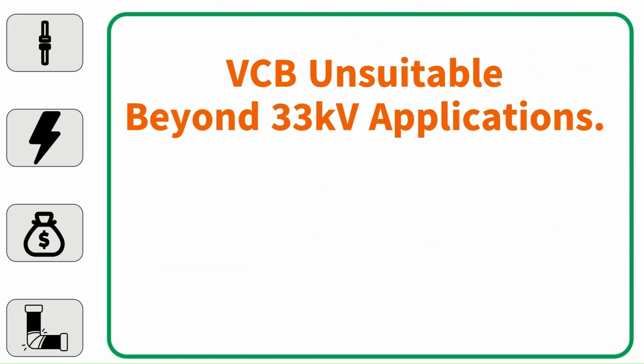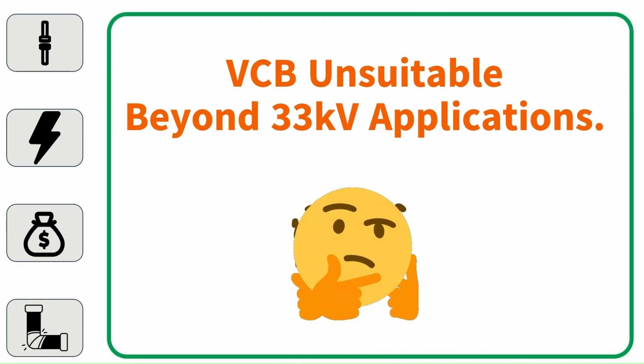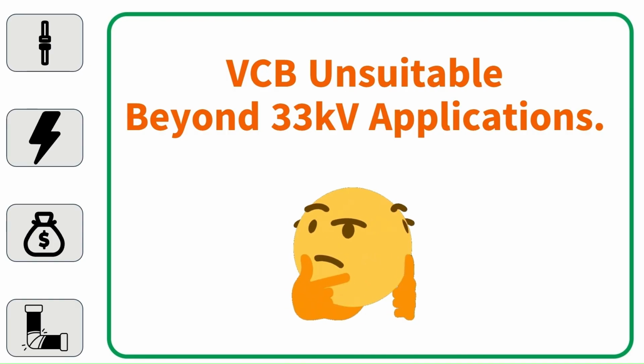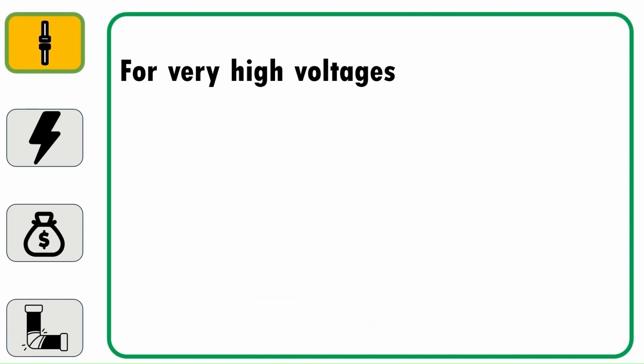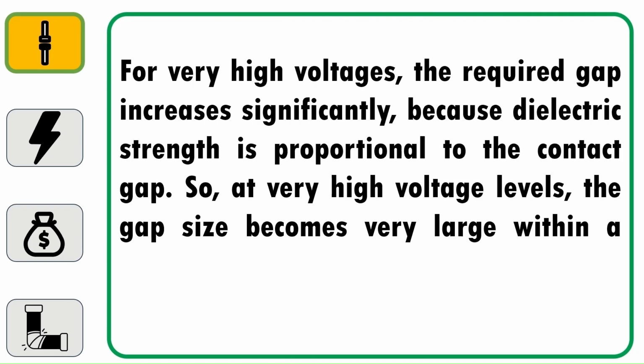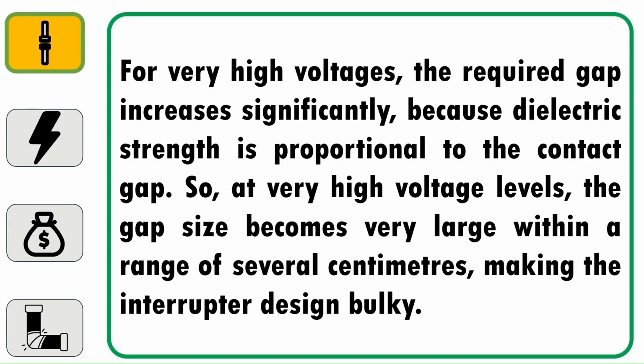Despite all these advantages of VCB, there are certain limitations that make vacuum circuit breaker unsuitable beyond 33 kV applications. For very high voltages, the required gap increases significantly because dielectric strength is proportional to the contact gap. So, at very high voltage levels, the gap size becomes very large, within a range of several centimeters, which makes the interrupter design bulky. The large contact gap requires a long travel distance for the moving contacts. Covering this long travel distance within the first 2 to 3 cycles of current is also challenging.